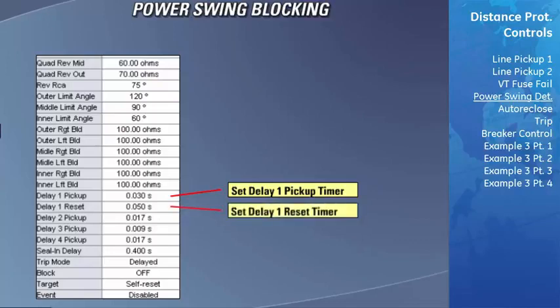The power swing reset delay 1 setting defines the dropout delay for the power swing blocking signal. When the impedance locus leaves the outer characteristic, the power swing reset delay 1 timer is started, and the block is held on until this delay expires. This setting should be selected to give extra security for the power swing blocking action.